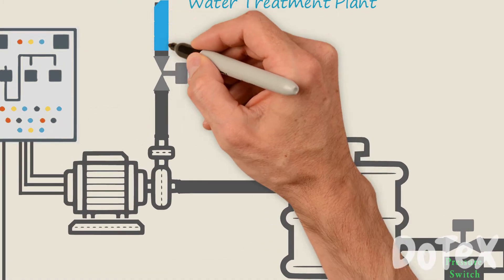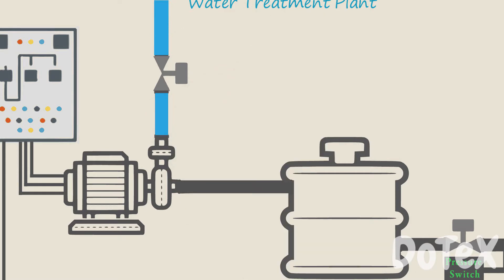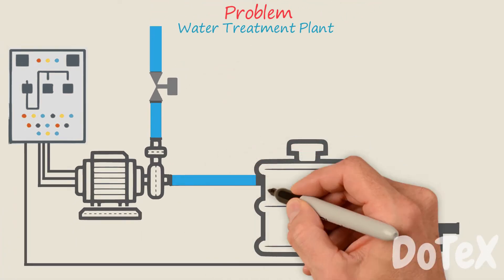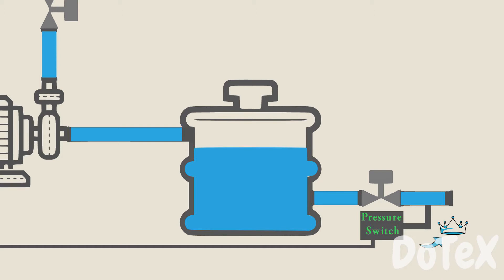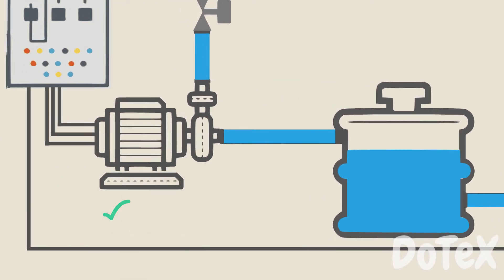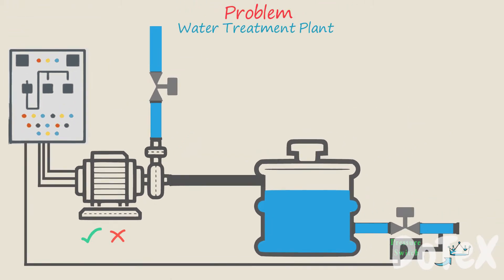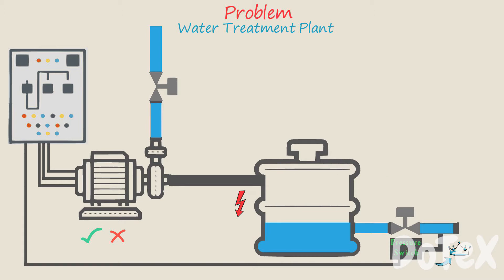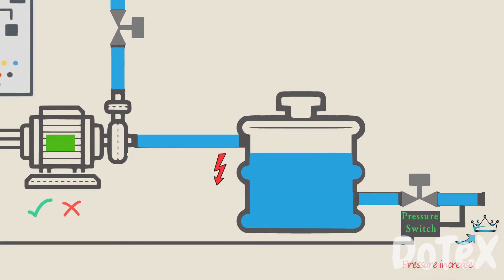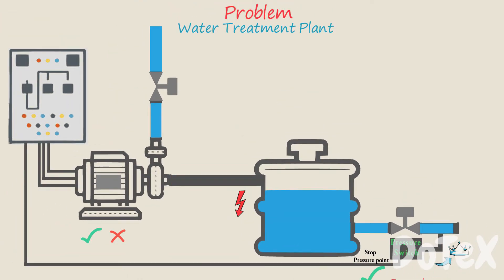A water treatment plant usually has a constant flow of water coming into the plant. The pump moves water into the pressure tank, and the pressure switch is the control unit for the system, ordering when the pump will start or stop. When pressure in the water system drops to a predetermined set point, the pressure switch tells the pump to start working. The pump moves water from the incoming water pipe into the pressure tank. The pressure will increase until the stop pressure point is reached, and the water pump will be turned off by the pressure switch.